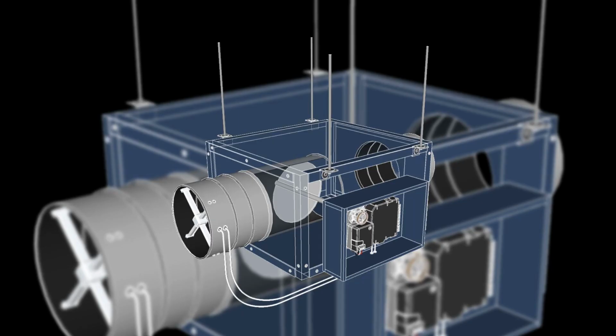Key requirements in SCA projects. Now, let's talk about what the School Construction Authority requires. VAV boxes have to be factory assembled and certified. They come with BACnet digital controllers and velocity sensors so they can hold airflow steady no matter what the duct pressure is. Controllers are mounted outside the box to make service easier. The box itself is built from galvanized steel with insulation and acoustic lining, and the damper must have very low leakage. Controls must use native BACnet, not proprietary gateways, and they need to tie directly into the school's automation system for alarms and monitoring. Many boxes also come with hot water reheat coils, which kick in during cold weather to add heat at the classroom level. And finally, the adhesives and sealants used in these boxes must meet indoor air quality standards set by SCA QMD and LEED.